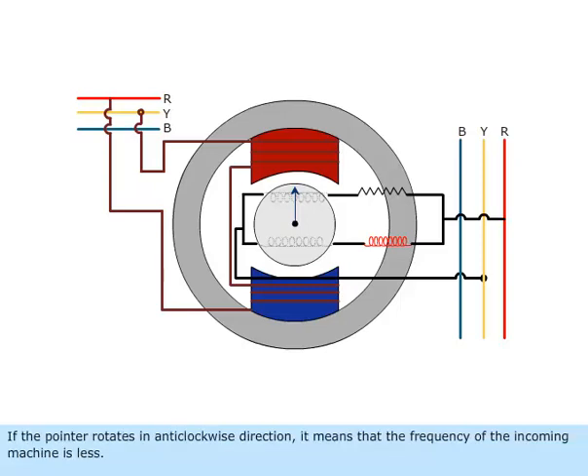If the pointer rotates in anticlockwise direction, it means that the frequency of the incoming machine is less. If the pointer rotates in clockwise direction, it means that the frequency of the incoming machine is more.